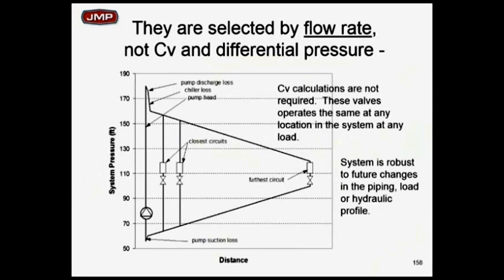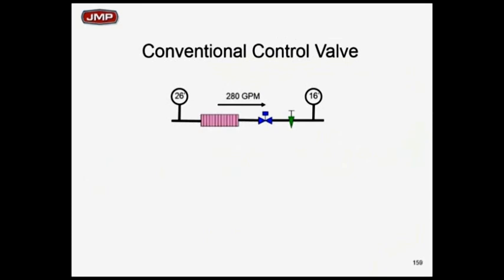Putting all this together, two-way valves properly picked should be picked on valve authority, rangeability, and CV every time. And the ones closest to the chill water plant have to have a much higher valve authority, much bigger pressure drop across them to make them open and close properly. Hard to do, not impossible, theoretically possible, but kind of hard to do in the real world. So that's why we want to look at pressure-independent control valves. Let's see if we can get this message across to you.